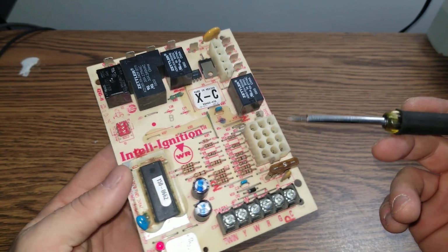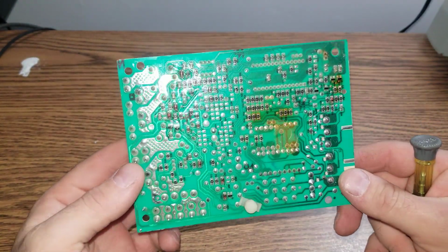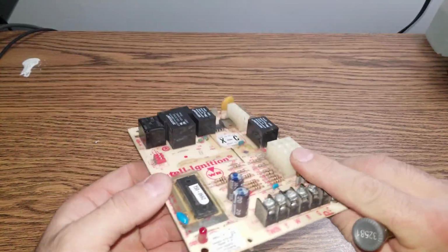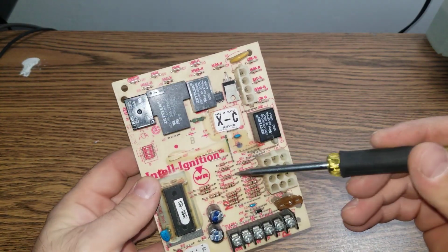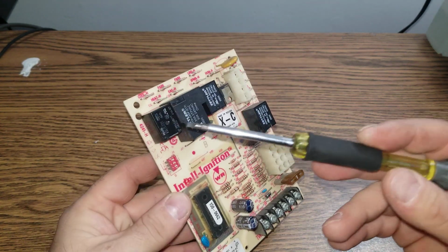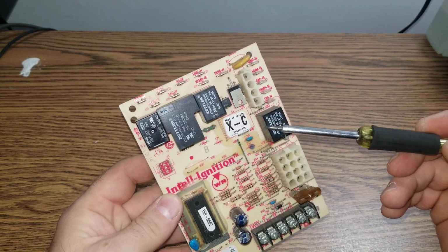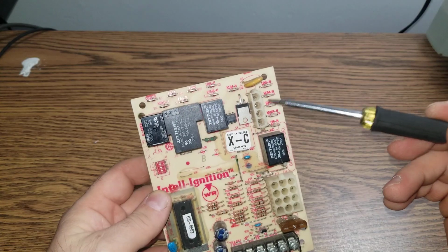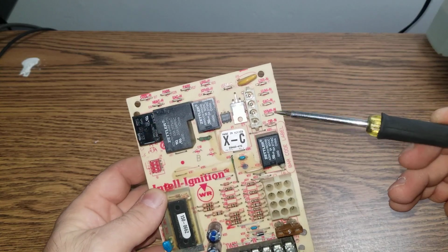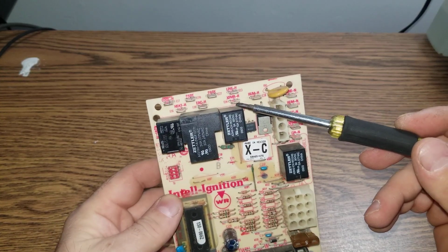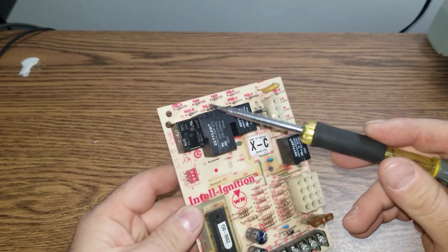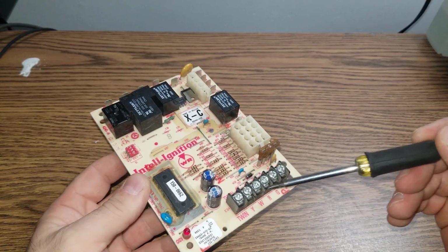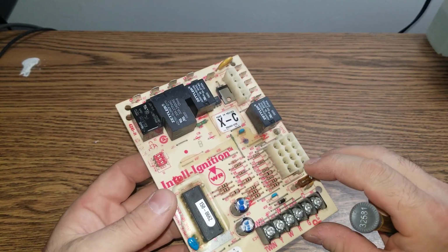And again, the whole purpose was just to simplify and not to make a big deal out of these boards. The different brands have different boards. Some of them have a separate flame safety connection here and other functions, but all of them have several relays for heavy loads, as well as neutral connections, high voltage connection, and connections for the blower motor. This is all essential, as well as low voltage connections.